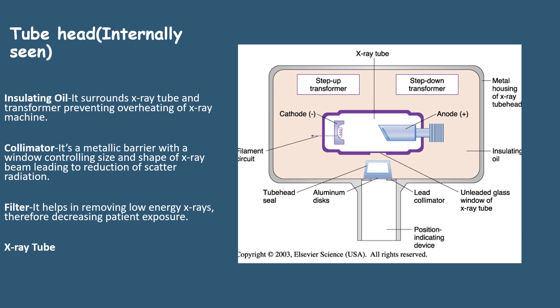The collimator is a metallic barrier. Its function is to control the shape and size of the x-ray beam so that there is lesser scatter radiation. This metallic barrier has a window. As we can see, this is the collimator and this is the window. When the rays pass through this, it controls the shape and size so that there is lesser scatter radiation.